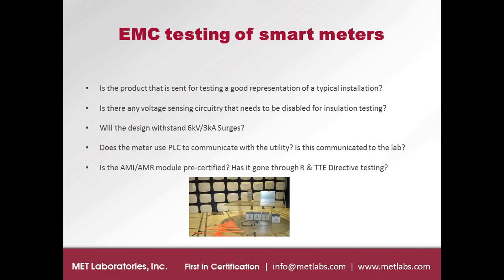Is there any voltage sensing circuitry that needs to be disabled for insulation testing? When we perform insulation testing, we perform it across various coupling paths like line 1 to ground, and so forth. And we do ask manufacturers before we perform this test, do you have any MOVs, any supplies, any transformers that are in line in any of the coupling paths that we are about to test? If so, we ask them for the locations, and we then remove those components before we proceed to perform the test. And in cases where we cannot do so, we don't perform tests on that coupling path. But that is something that we need to know before we perform the test.